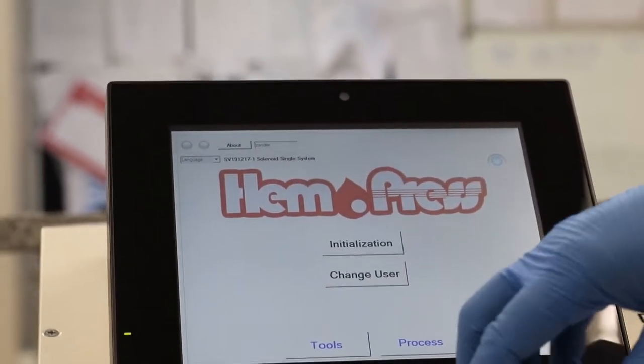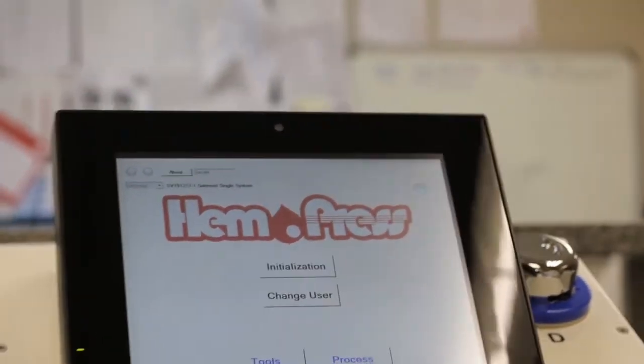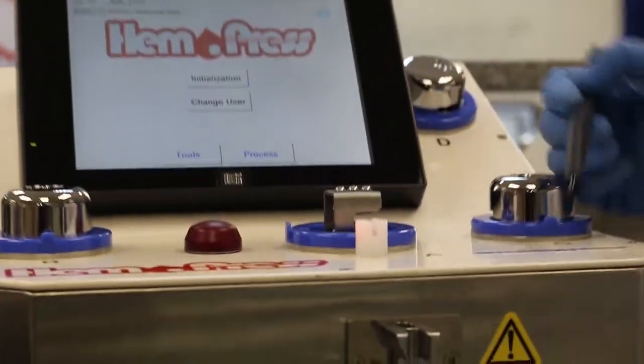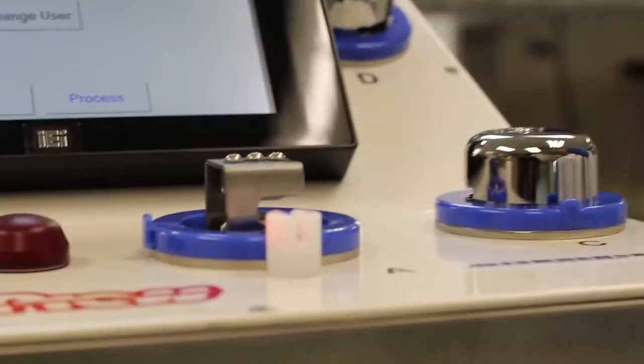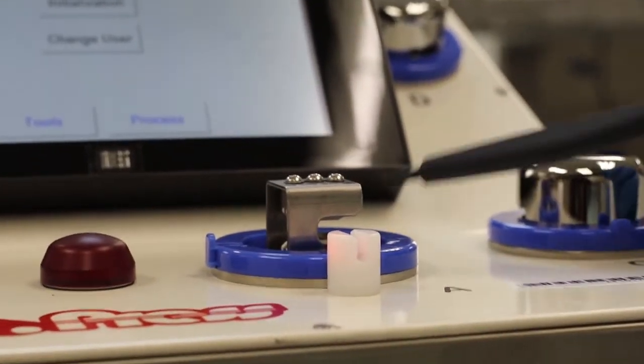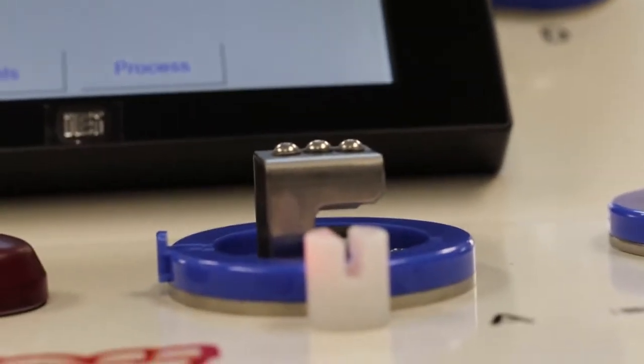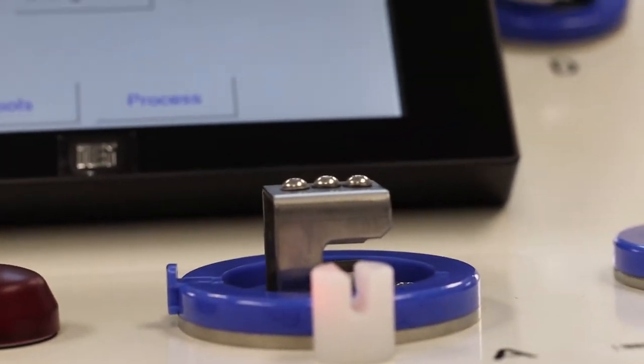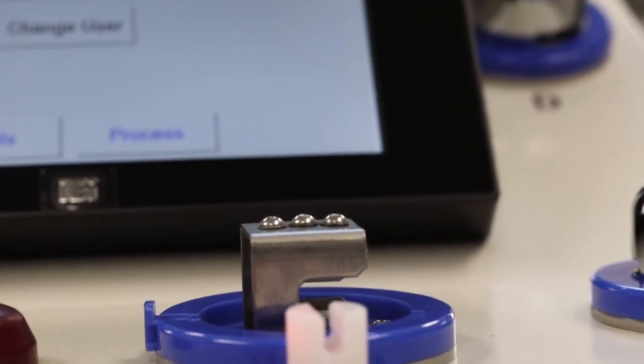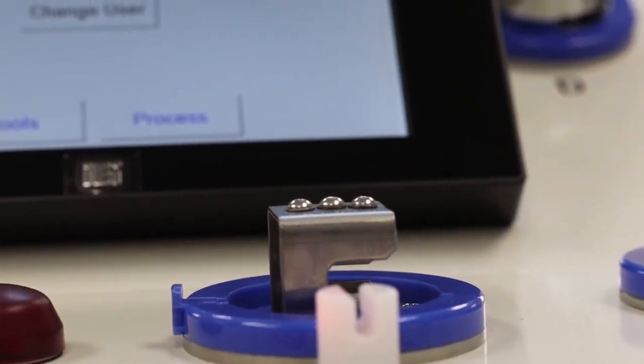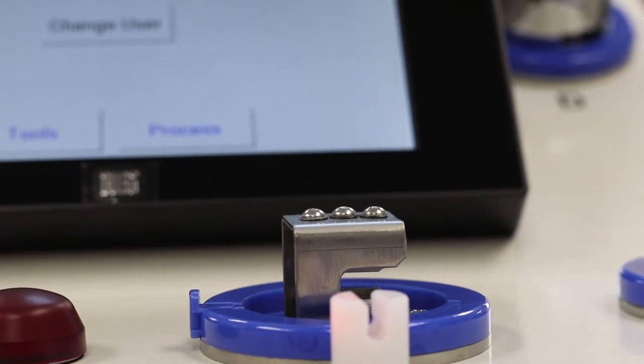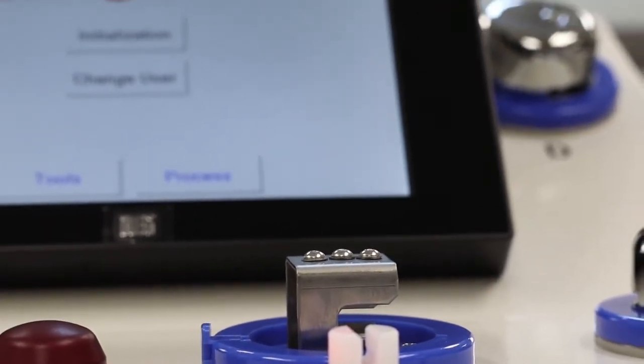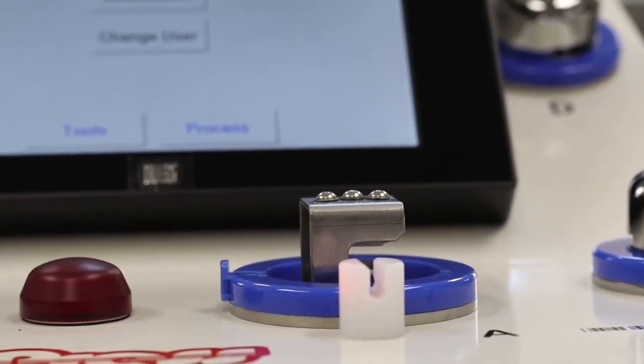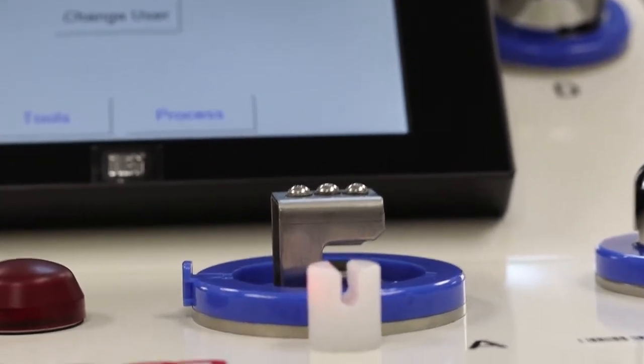For your clamps, just for a closer look, we slide in our tubing. First of all, it will detect your tube. If there's no tube, it will alert you that there's no tube. The second thing is the opening and closing of the clamps to determine which component will be pressed out, plasma or red cells. And lastly, it will also seal your tubing for easy breaking afterwards.